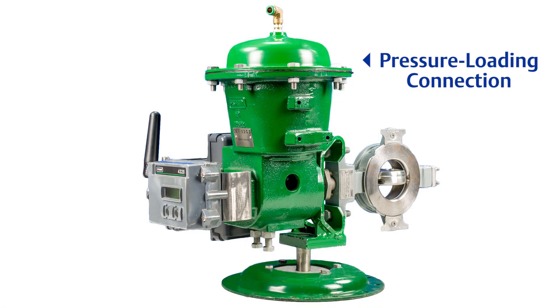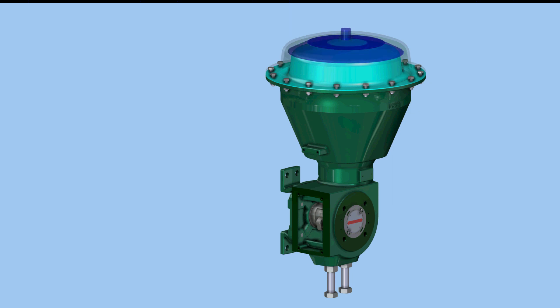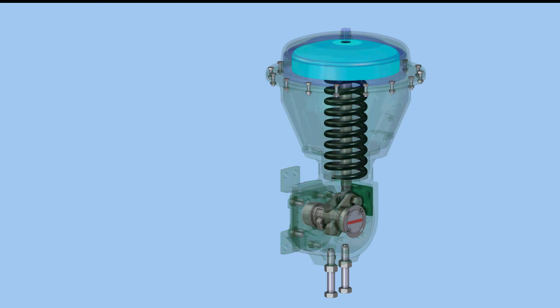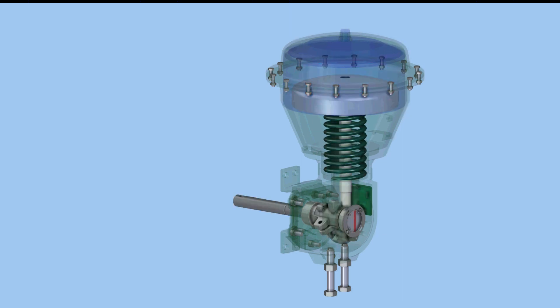The pressure loading connection is always located on the upper diaphragm casing. As pneumatic pressure is increased, it's applied to a diaphragm which transfers the force to a diaphragm plate. The diaphragm plate is connected to the actuator stem, which connects to a lever that turns the valve drive shaft.